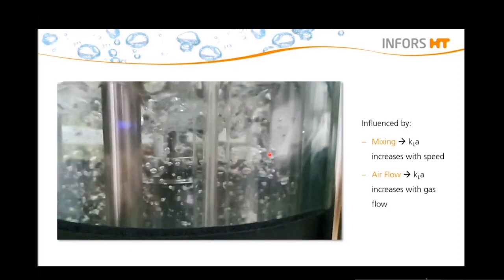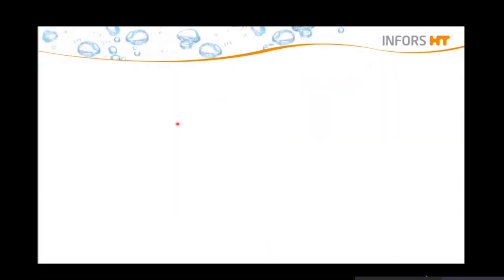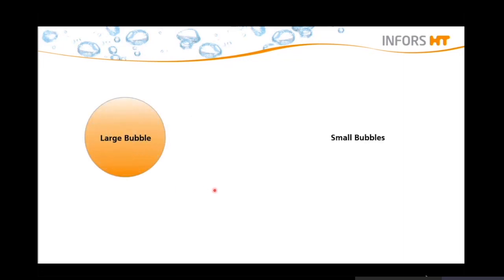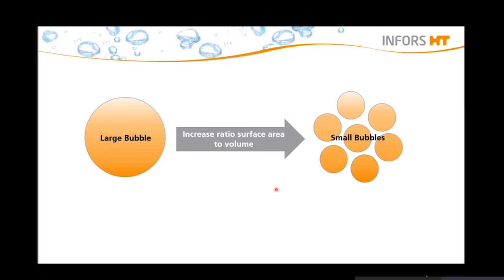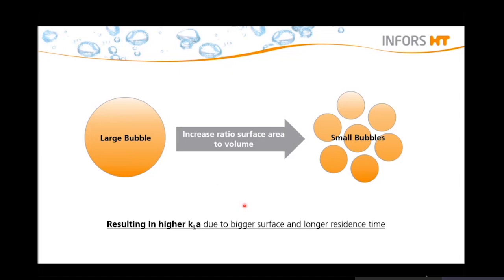But why exactly are smaller bubbles needed? A bigger bubble has a smaller surface compared to the surface of all the small bubbles together, but they still have the same volume as you can see in this illustration. So they need the same space inside the bioreactor, but the large bubble has a smaller surface. By shredding the bubbles, we can increase the ratio from the surface to the volume, and thereby the KLA is higher, giving us a better oxygen transfer.